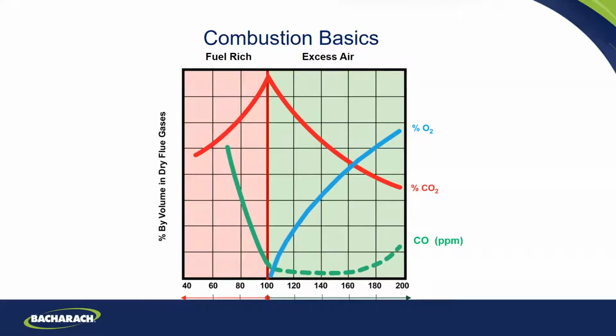And then I would put an overlay on this. As I talked about, this is percent by volume of gases here, your CO2 and your oxygen. This green line I put in here is carbon monoxide, that deadly gas we will talk about later. We can't do it in percent by volume. 1% by volume equals 10,000 ppm of any gas. If we measured CO by percent by volume, by the time the meter read 1, everyone would probably have passed away in that building. So we do it in something a lot lower called parts per million, ppm. So 8% CO2 would equal 80,000 ppm. Here this would be an overlay, and we're reading CO in ppm, a very low quantity.